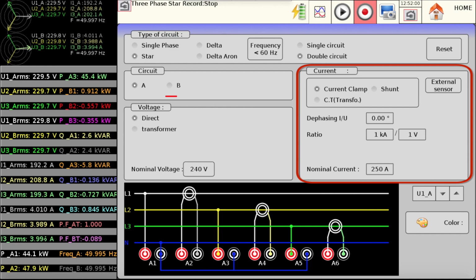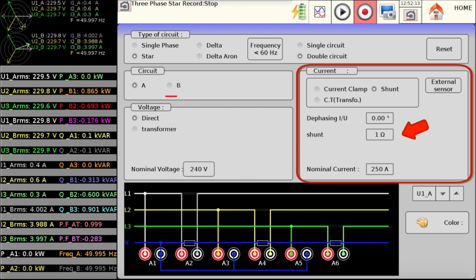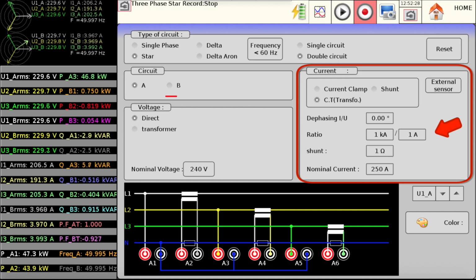The current can be recorded in different ways, via a clamp, a shunt, or via a current transformer. In the case of a shunt, you can directly enter the value of the shunt in ohms and the dephasing between I and U to have more accurate values. In the case of a current transformer, you can enter the ratio between the primary and the secondary current of the transformer and then the value of the shunt to be able to enter a voltage on the recorder.